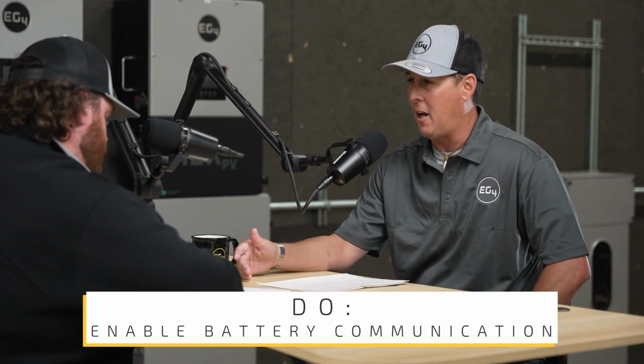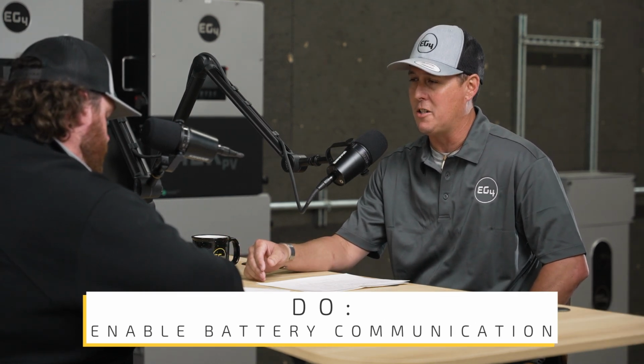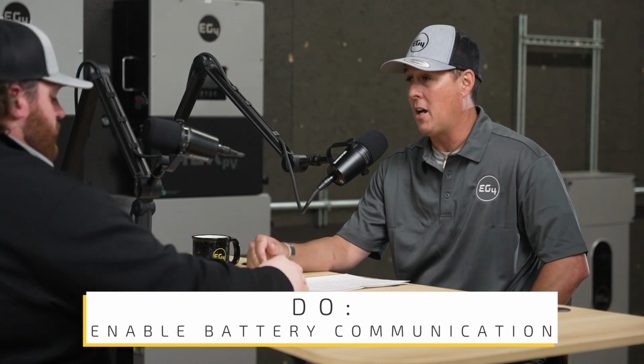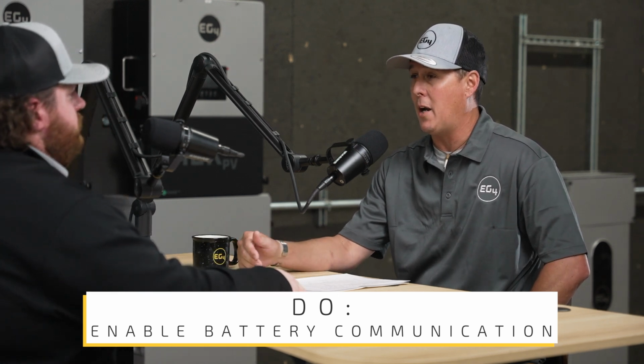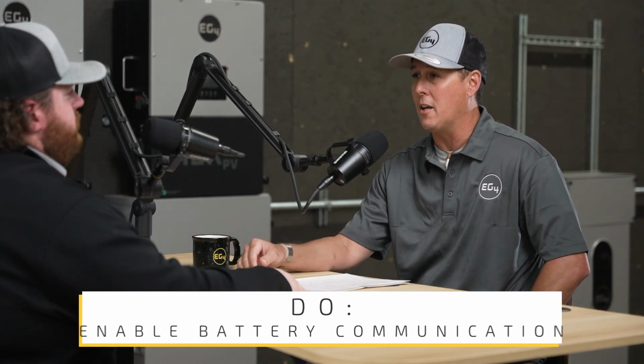Enabling battery communication, again going back to the installation manual, we see this all the time: guys not sharing battery banks between inverters or having imbalanced legs. Say you had 2 inverters and 4 batteries, they may put 3 batteries on one inverter and 1 on the other, creating an imbalanced load.